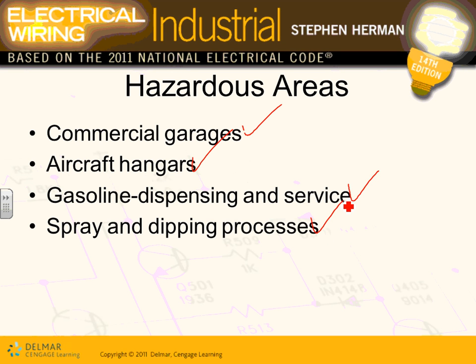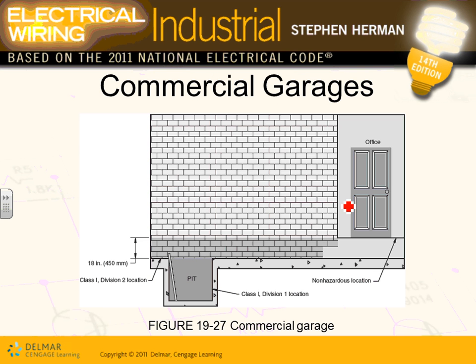Do you guys remember when we went to, where did we go? Did you see where they were dipping all these parts in paint and moving them into the oven? That's a hazardous location, a spray area. That's dust. Class 1 and class 2. There could be dust and gas in them. So these locations, the code book has 5-6 locations classified as hazardous locations: aircraft hangars, garages where they fix your cars, gasoline, gas stations, spray and dipping areas.